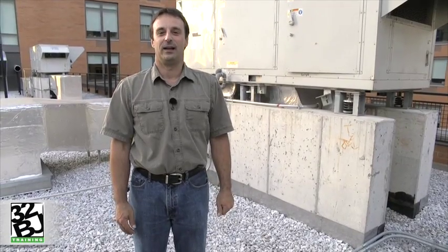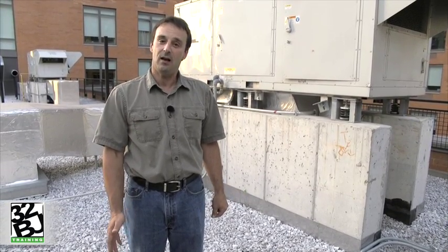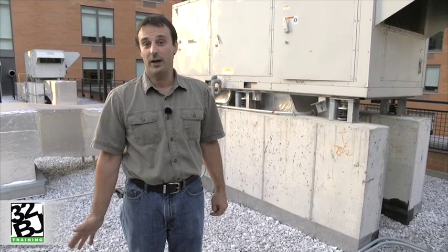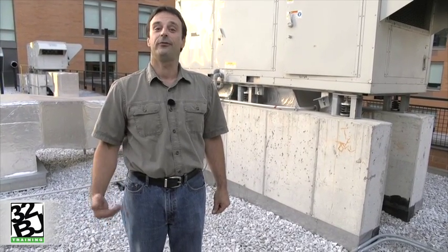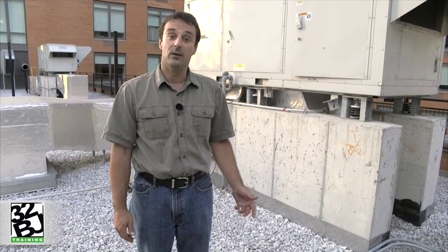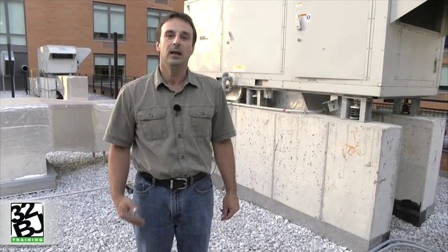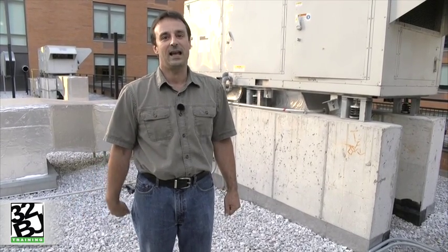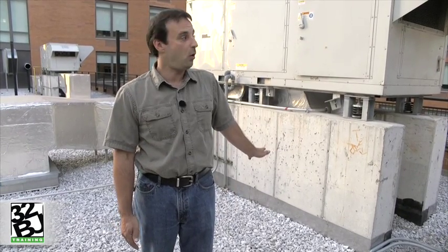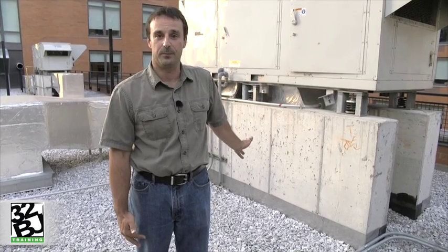The hallway ventilator is a completely self-contained machine. Its design is to bring in outside air year-round, 24/7, to provide fresh air for ventilation into the common hallways. In the wintertime, that air will be cold, so the hallway ventilator heats that air with a gas-fired heating chamber. And in the summertime, this hallway ventilator will pre-cool the air with an air conditioning system.